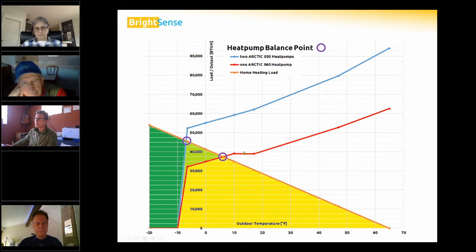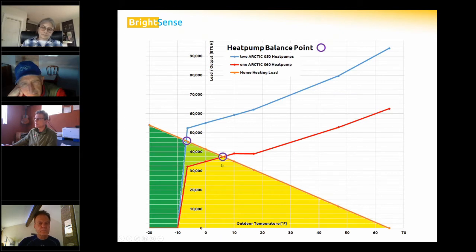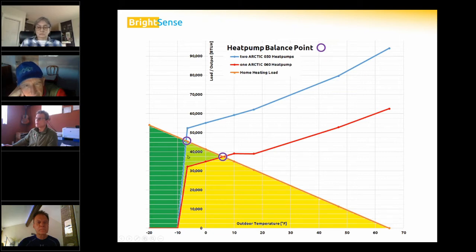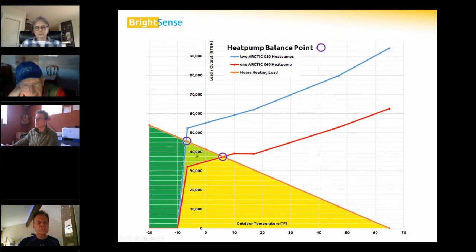The heat pump is able to heat the house up to the balance point temperature — in this case about five degrees. Below five degrees, we'd need supplemental heat to deliver the difference, once the heat pump is no longer able to keep up.